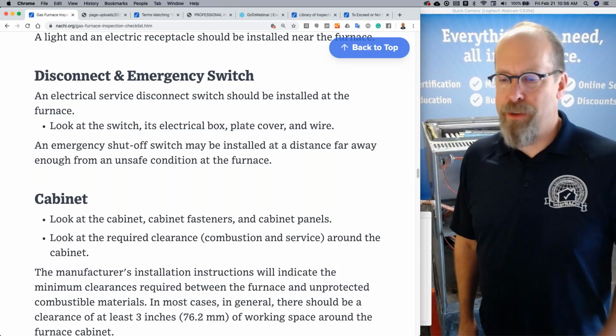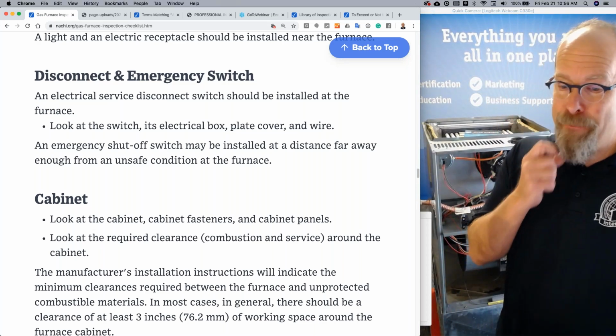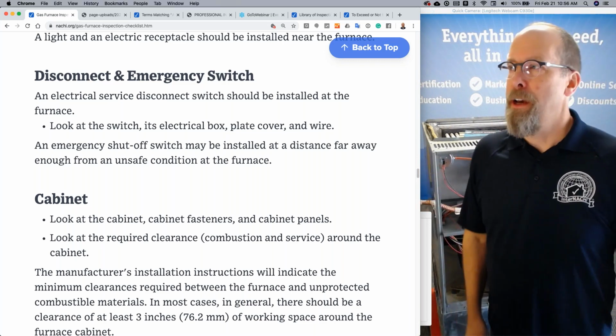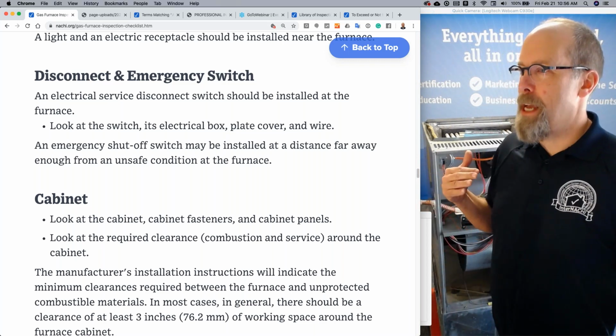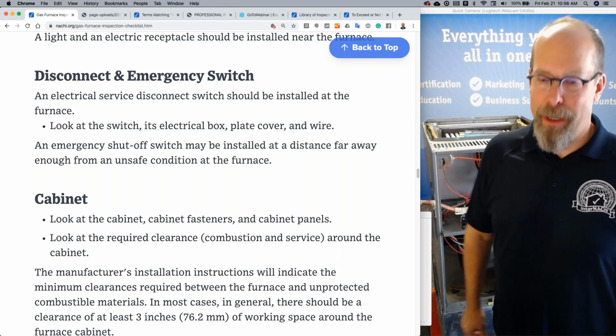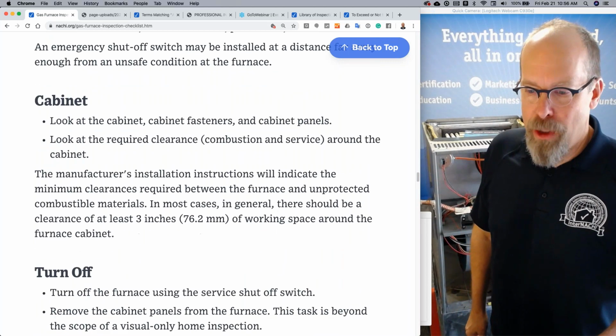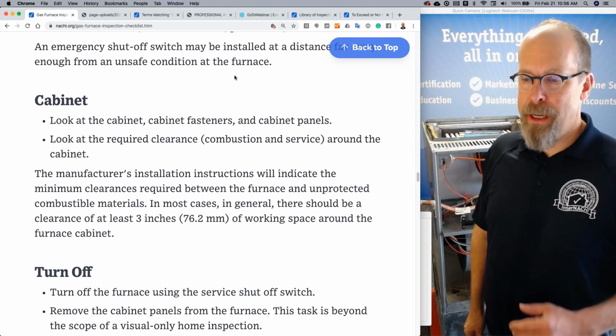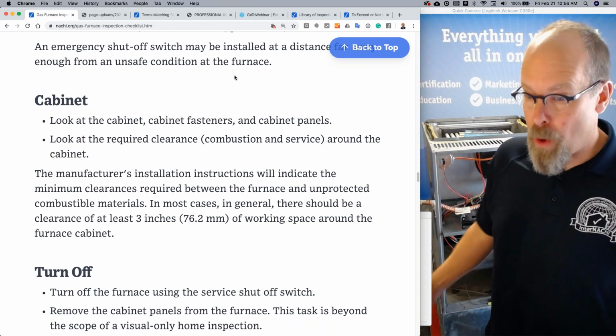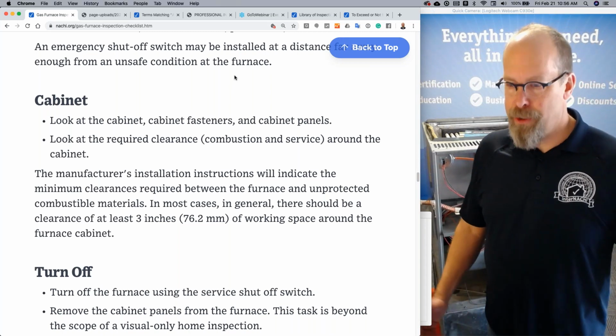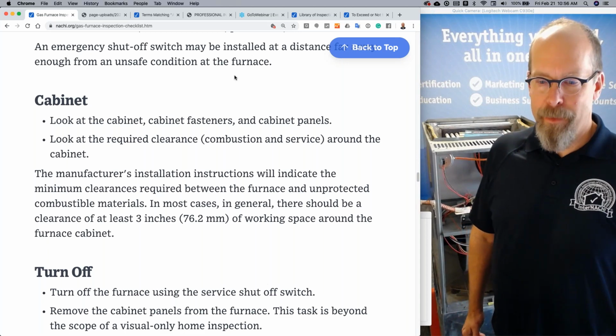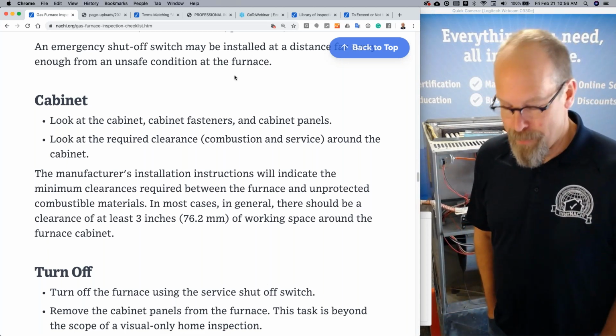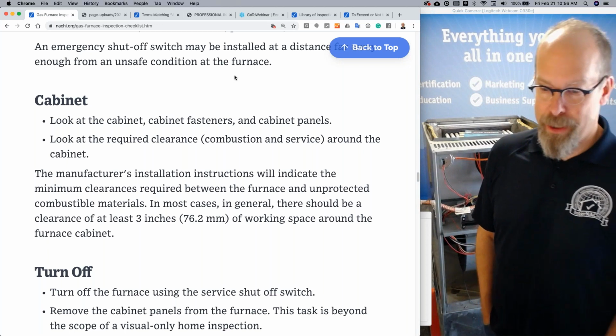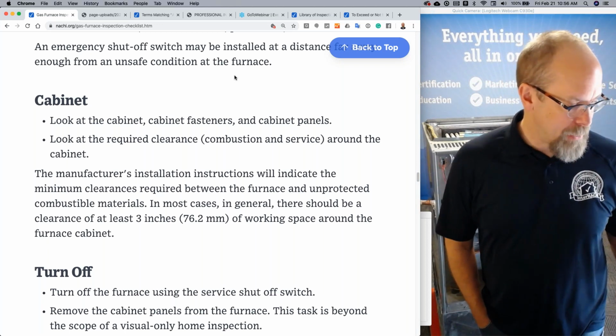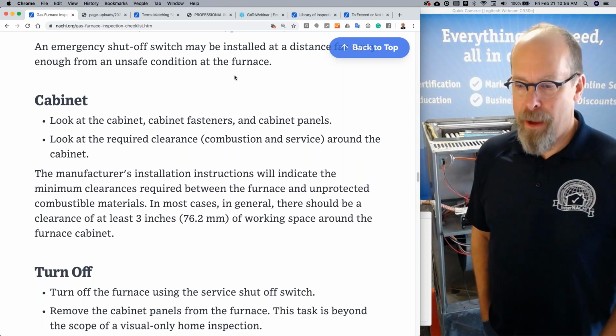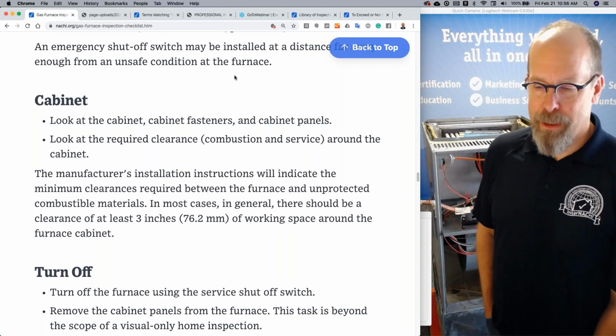An emergency shut-off switch may be installed far enough away from an unsafe condition at the furnace. Where I inspected, it was at the top of the basement stairs, and the furnace is down in the basement. Cabinet: look at the cabinet fasteners and cabinet panels. Look at the required clearance, combustion and service, around the cabinet. The manufacturer's installation instructions will indicate the minimum clearances required between the furnace and the cabinet and unprotected combustible materials.